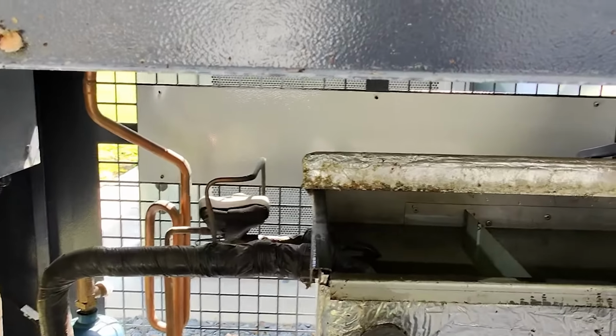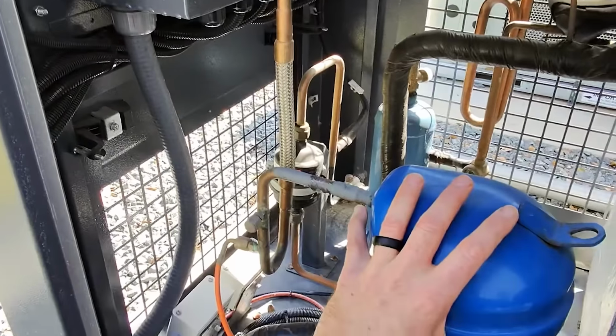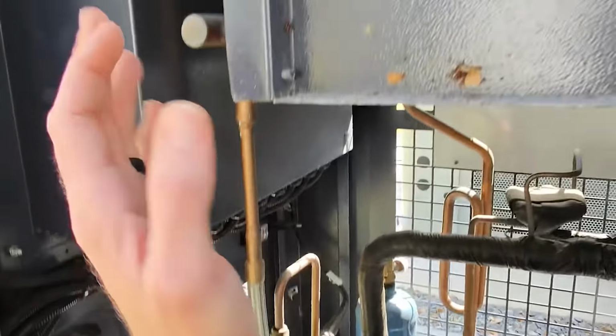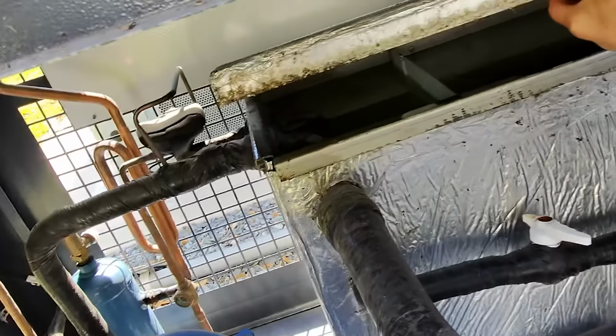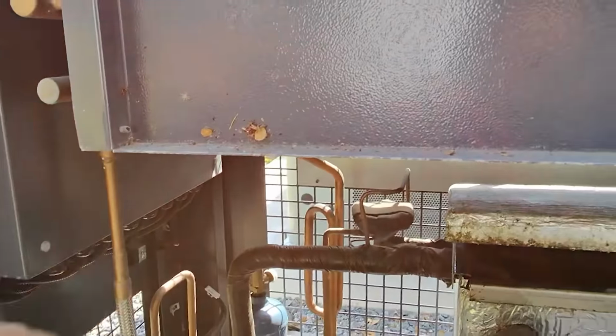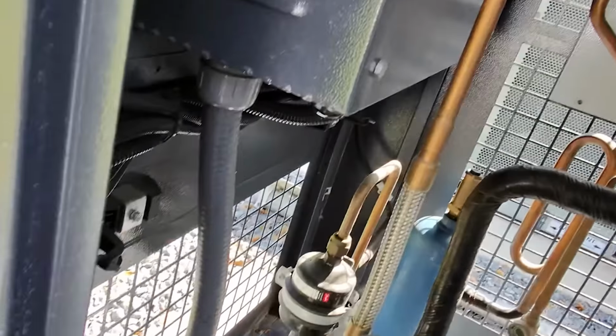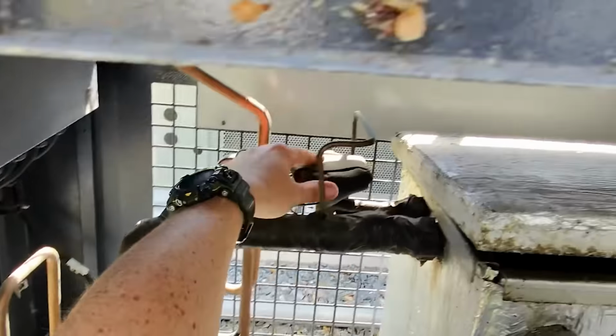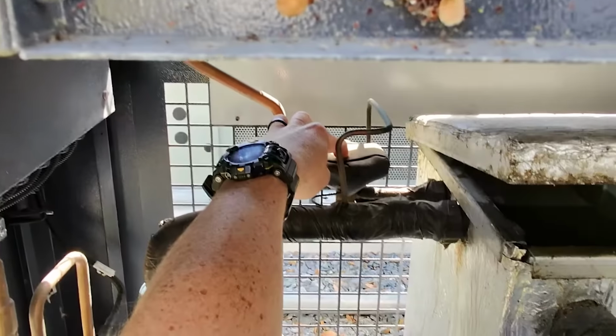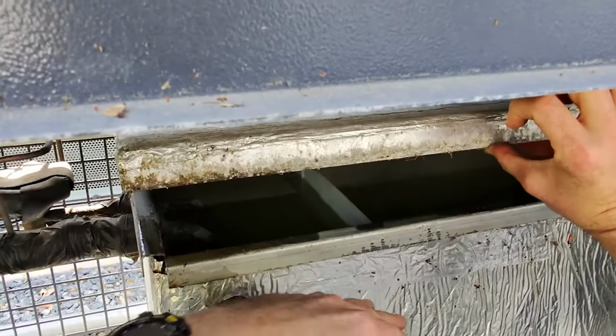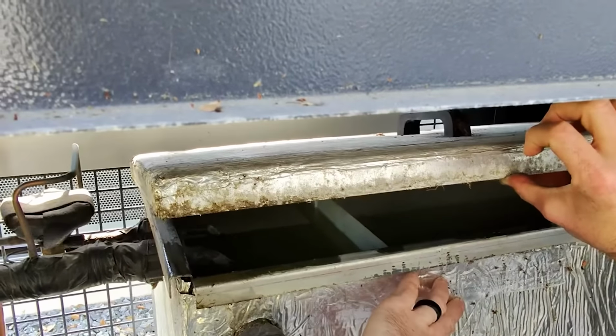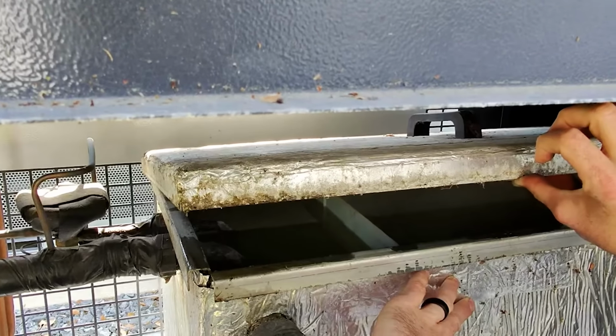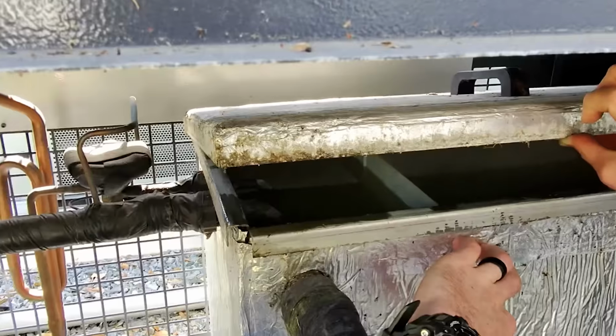So from what I can tell, right, compressor runs, hot gas goes up, goes to the heat exchanger outside, variable fan speed. Ramps up, ramps down to maintain head pressure to create liquid. That liquid then comes down, right, out over to what looks like a nice little liquid receiver that then comes back up and around through sight glass to what looks like our metering device, our TXV, that goes into the, we'll say, adiabatic cooler here. It's this tank of water that's designed to remove the heat from the water from inside.